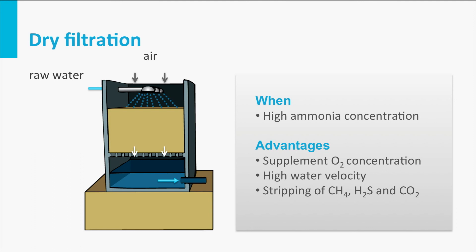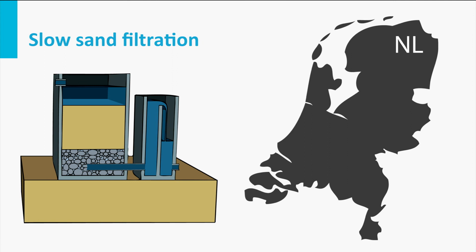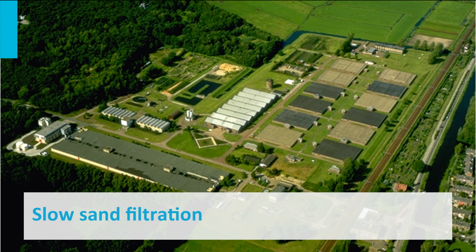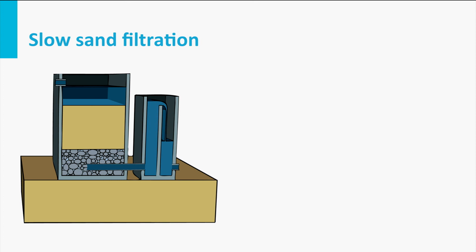The oldest type of filtration is slow sand filtration. For more than 100 years these filters have been used and continue to be used today. In the Netherlands, they contribute to disinfection of drinking water and remove biodegradable organic matter to obtain biostable drinking water that can be distributed to consumers without dosing chlorine. Slow sand filters are operated at very low velocity and thus require large surface areas, especially compared to rapid sand filtration. Because of the small sand grains, clogging occurs on the top of the filter bed, resulting in a highly biologically active layer called the schmutzdecke. Instead of backwashing, scraping of this layer is performed as the cleaning method.